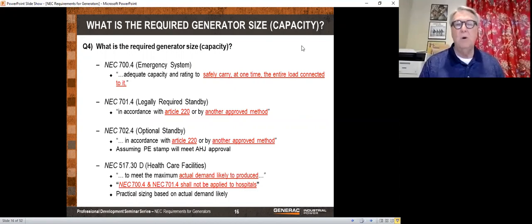It's not clear anymore. And it kind of irritates me that it seems like every time a National Electrical Code comes out, they make it worse. But at any rate, I'll quit complaining about that. What we would say is you just need to safely carry at one time the load that's actually connected to the generator and running. And so we would not put the spare in that. NEC 701, 702, this is your legally required and optional. Notice that they used to be entirely different and now they read entirely the same.